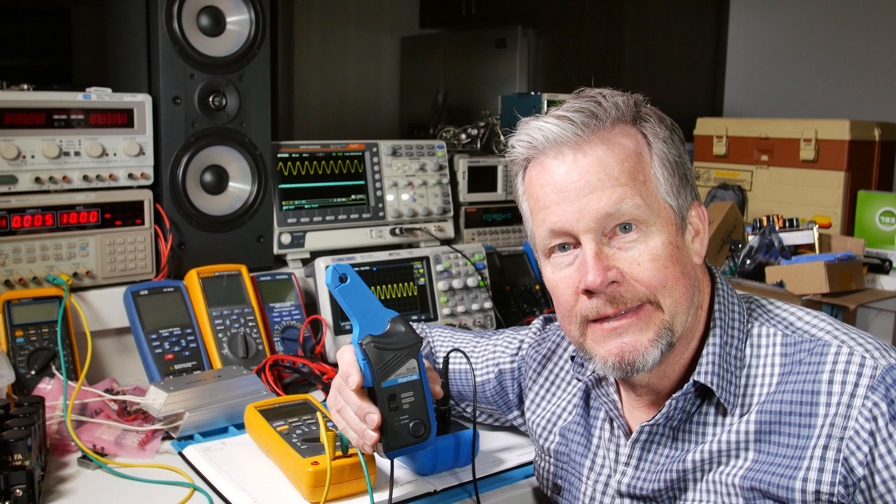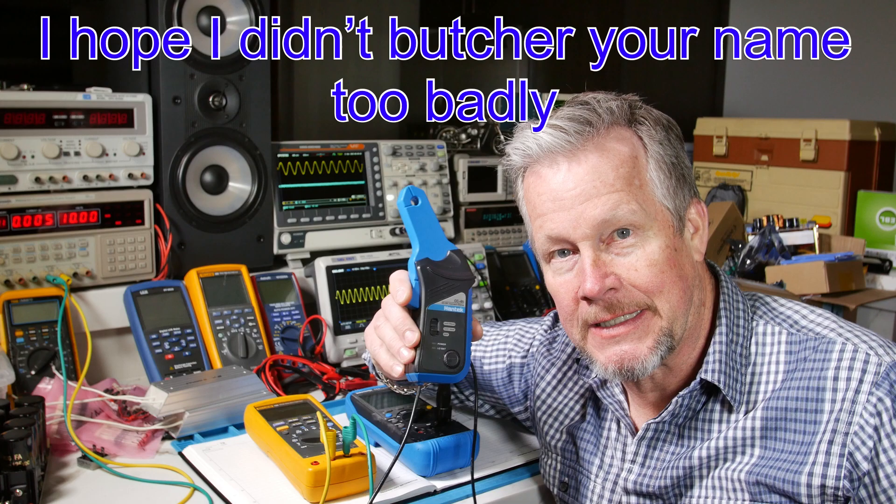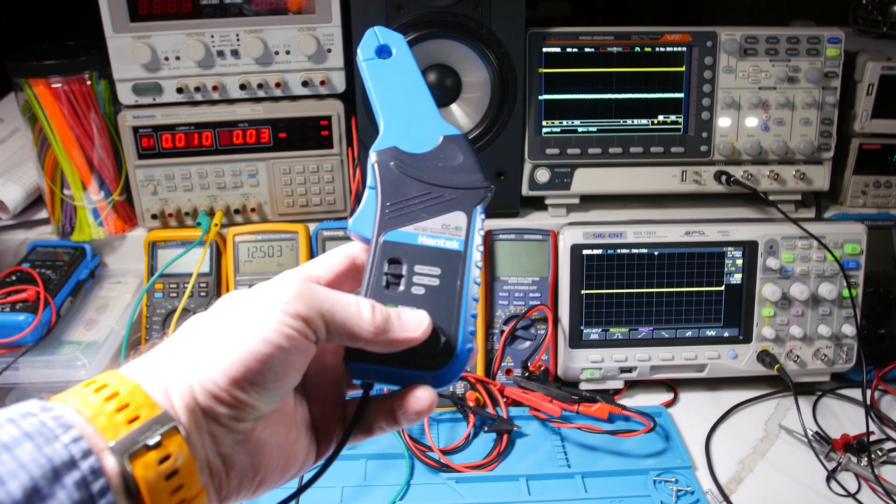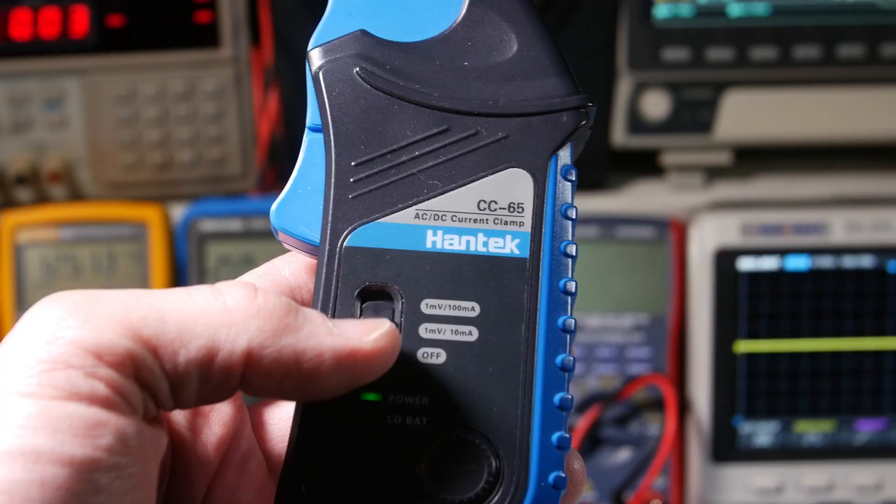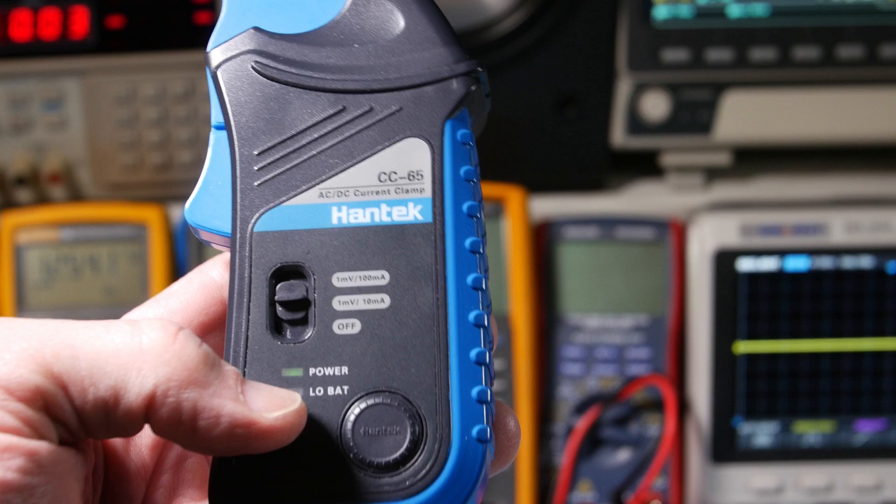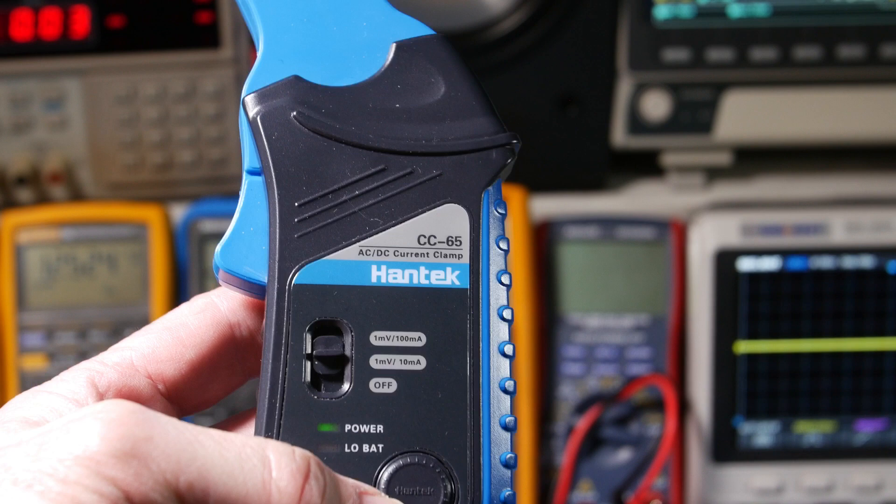Thanks Kadir for asking the question, and thanks guys for watching. Okay guys, here's the setup. Let me go over the meter first. I've got it set at the 1 millivolt per 10 milliamp setting. You see the green LED power on. Low bat light's not on, so it's a good battery. Here's the degauss button that we're going to be hitting a lot to reset it. At these low current readings, you've got to make sure you've got a good degauss.